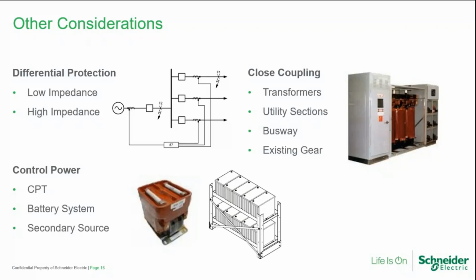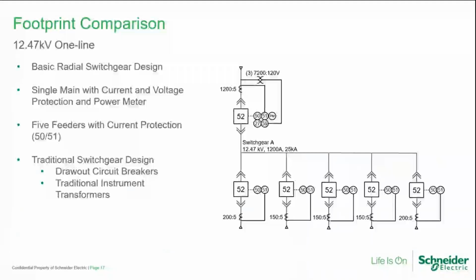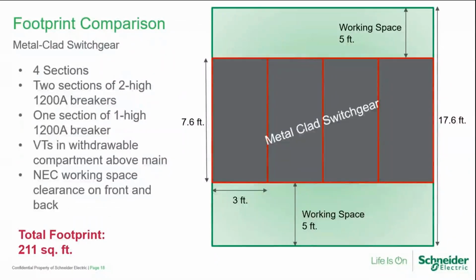All right, I'm going to keep moving because I want to try and get through some space savings examples that I have here, and then we'll do a little bit more question and answer at the end. So let's consider this 15 kV lineup: main breaker, 5 feeder breakers, a single VT associated with that main breaker. This is a very traditional basic radial main and feeder lineup. If I was doing this design with metal clad, this would look like 4 2-high sections. You'd use a main and a VT in the first cubicle, and then 2 sections of 2-high breakers, and then 1 section of a single high breaker.